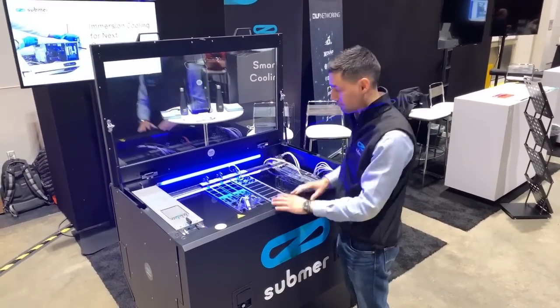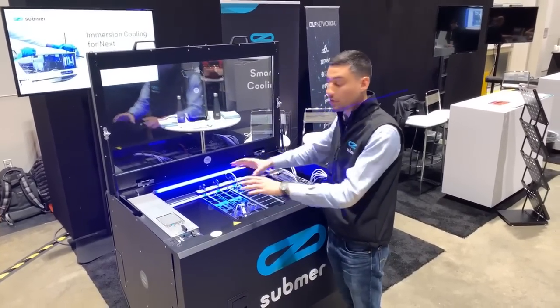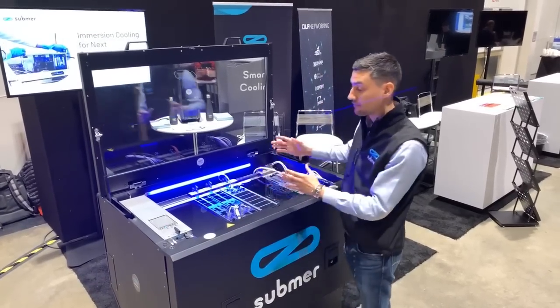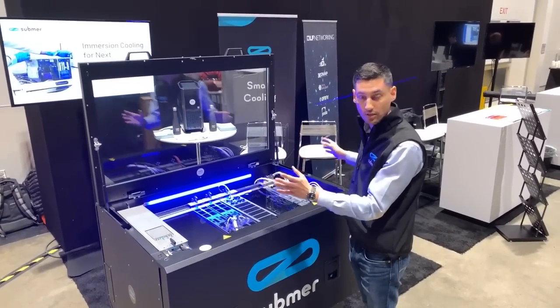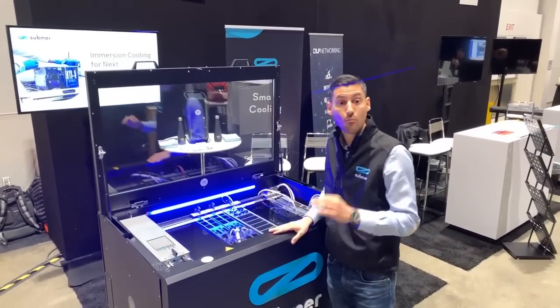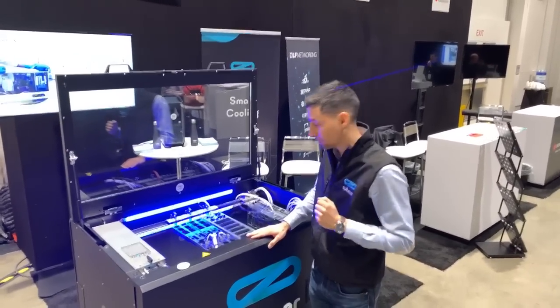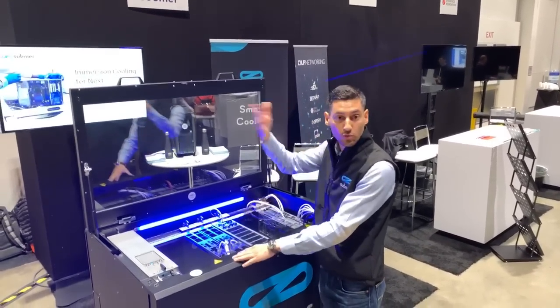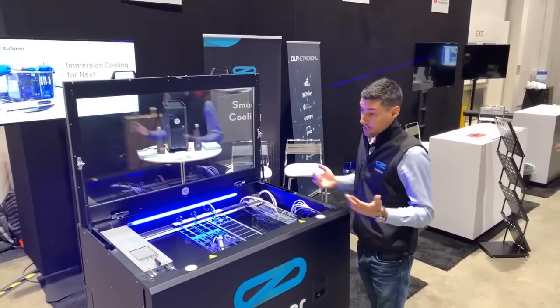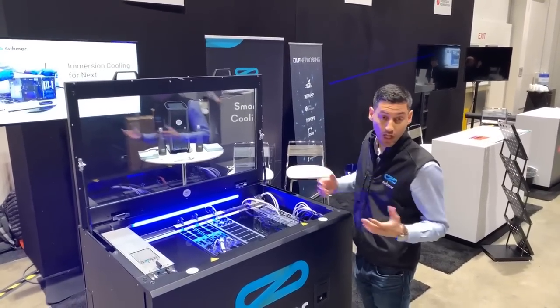This gives you several advantages. First, resilience — you can have not only redundancy per CDU, because we have a dual pumping system inside this small space, but you can have several CDUs per rack unit. It also allows you to increase the density. We can have more than 100 kilowatts, even in hot climates like the Middle East or Africa, and you can even go to more than 200 kilowatts in this small space — 20 to 30 times more density compared to the average rack.